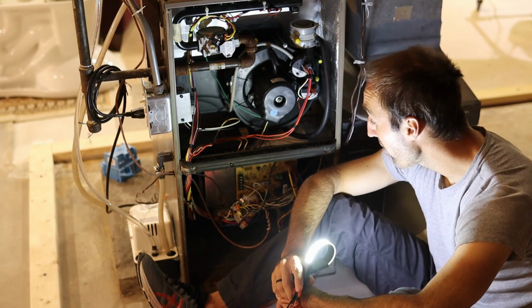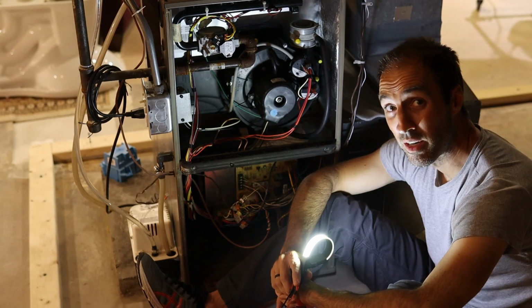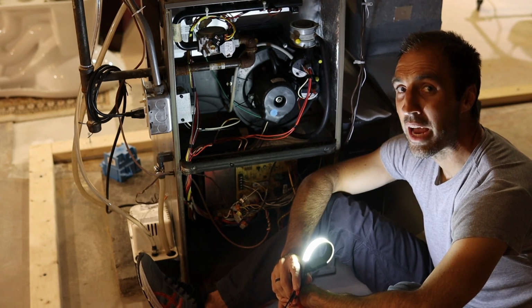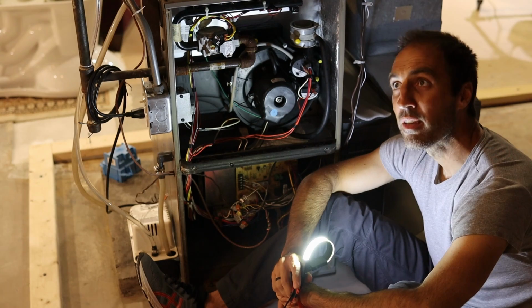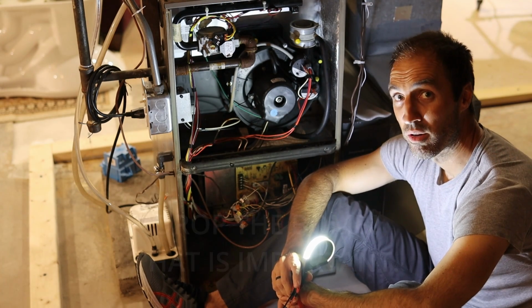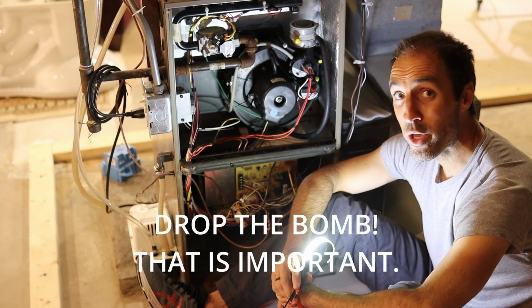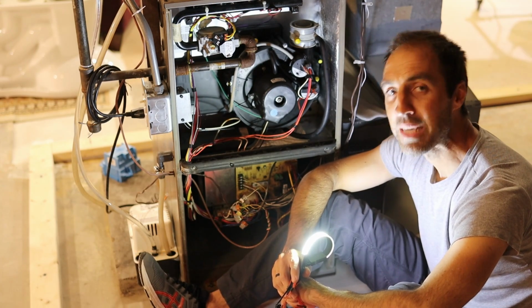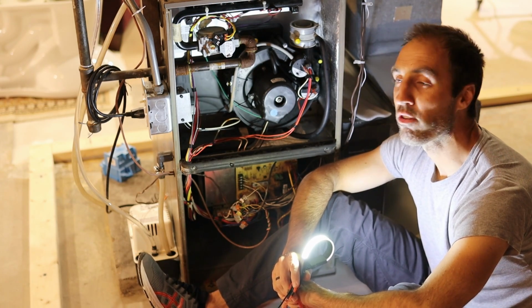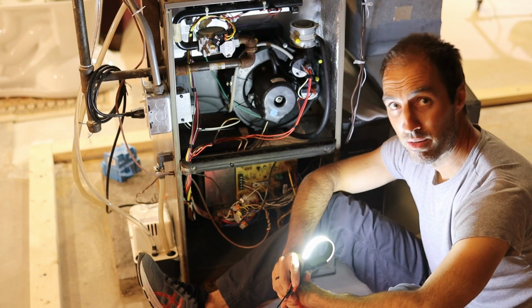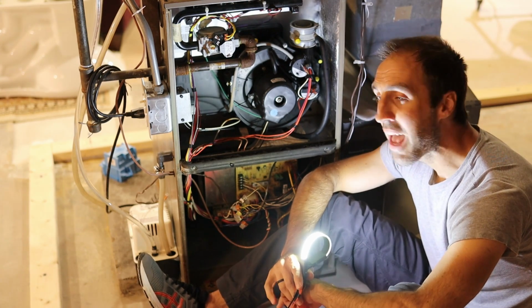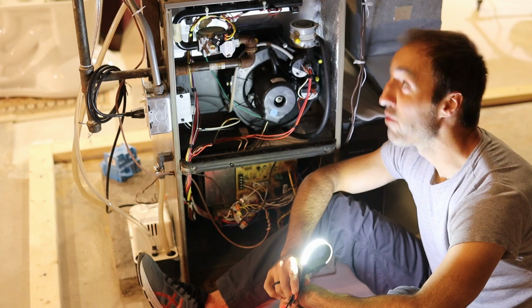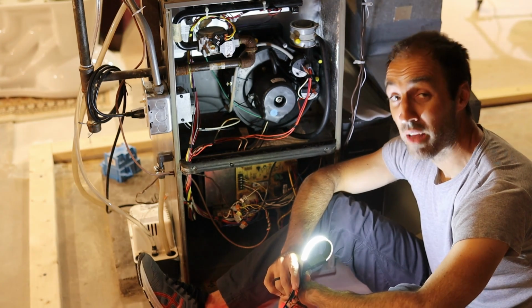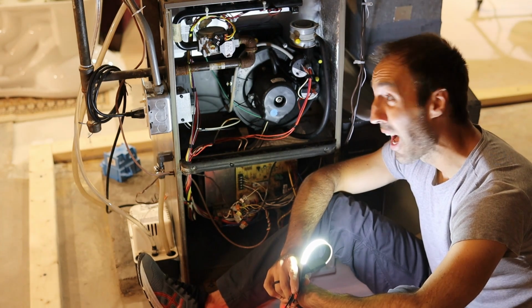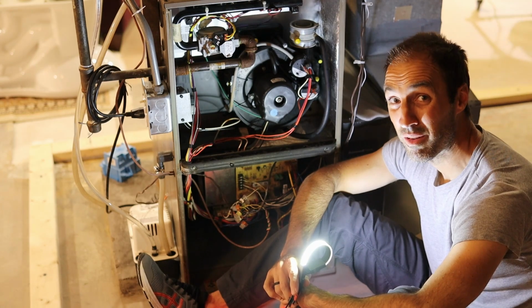So, you know how many CFM of air your blower can deliver, but it can deliver that much air against a given external static pressure. And you only know what your external static pressure is by measuring. If you don't measure, you're guessing. And you measure with something called a manometer. So you need to have a manometer and to measure the external static pressure in order to determine how much CFM is going through your system.